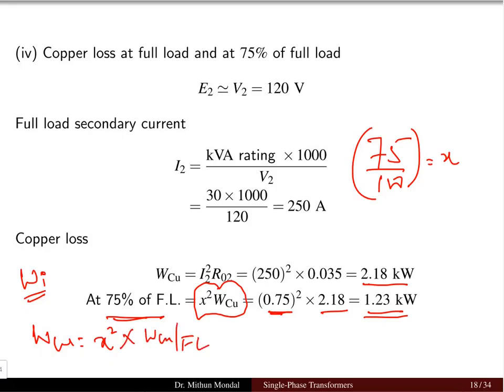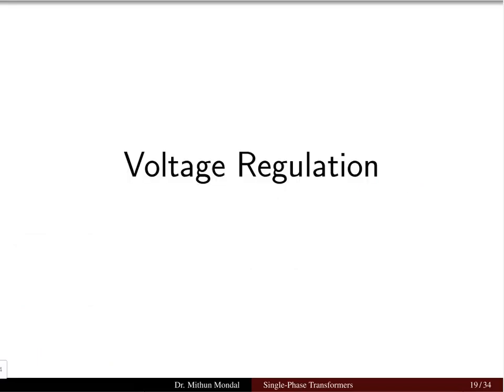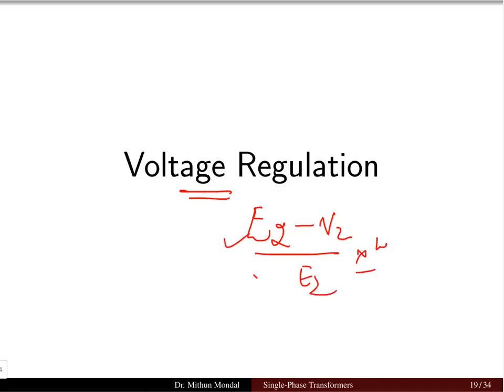The next part of this tutorial will be focusing on voltage regulation. We know we have seen in the lecture class that voltage regulation is basically E2 minus V2 by E2 into 100. So no load minus full load, this is no load, this is full load, this is no load into 100. That is the voltage regulation. And the voltage drop E2 minus V2 we can calculate from the equivalent circuit parameters.